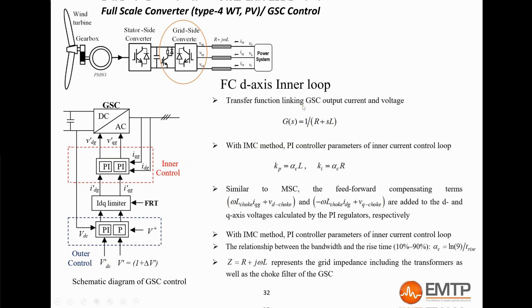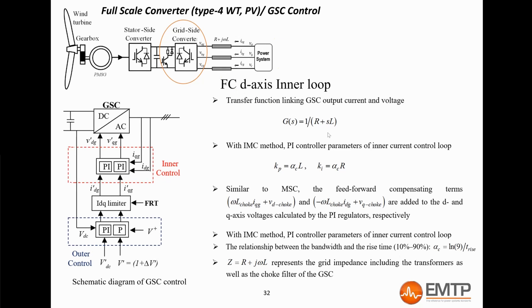For the grid-side converter, the gains of the inner loops depend on the total impedance seen by the converter. The transfer function is shown here, where R and L are the resistances and inductances of the choke filter, the converter transformer, the park transformer, and the grid Thevenin equivalent. In the generic model mask, the user can set the rise time, which determines the inner loop speed. It is typically set to 10 milliseconds. The voltage control is at the converter terminal, but the voltage measured is after the choke filter. Therefore, and similarly as the machine-side converter, a feed-forward compensation is done before putting the converter voltage reference back to the ABC domain.